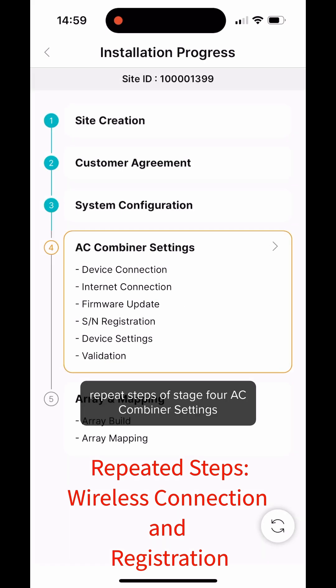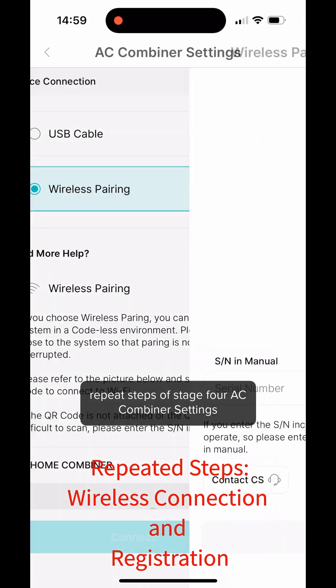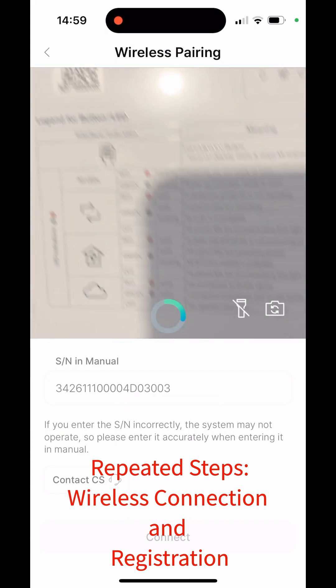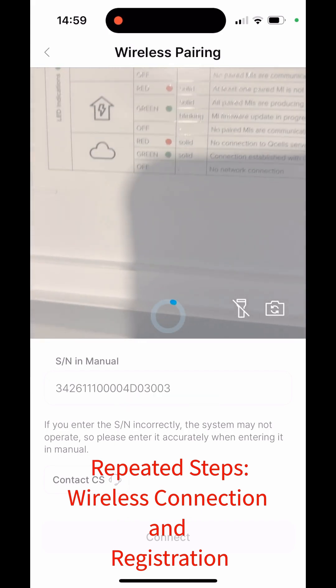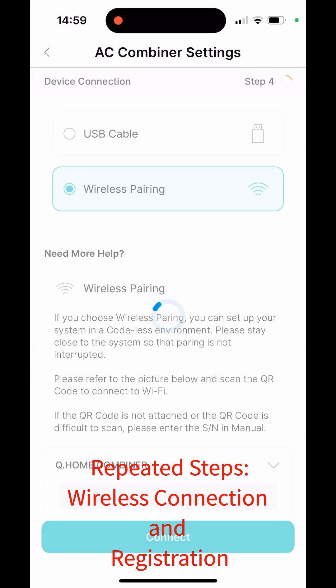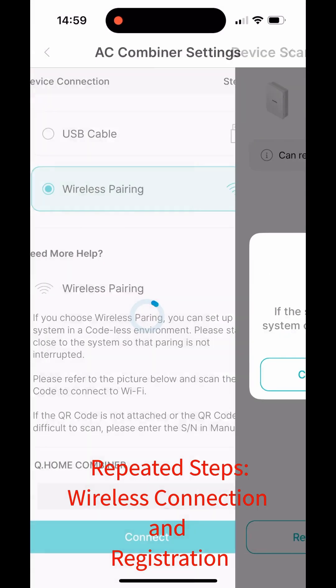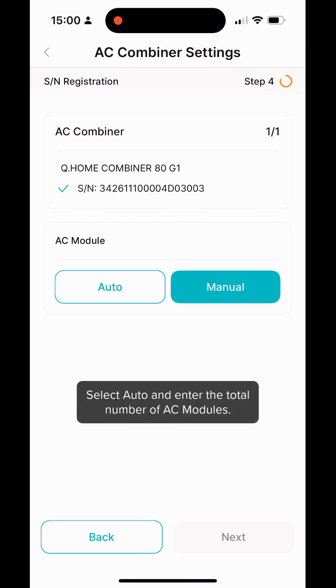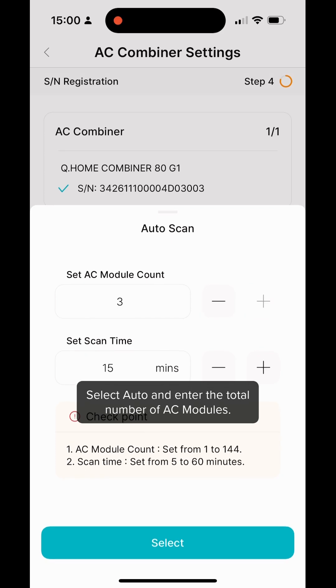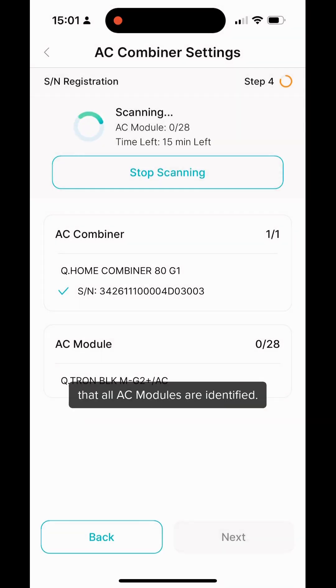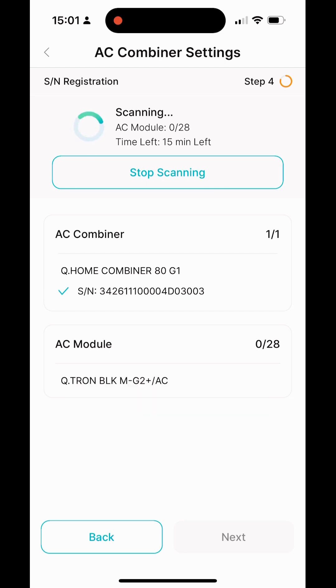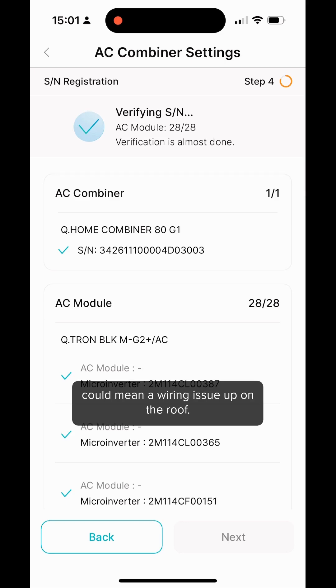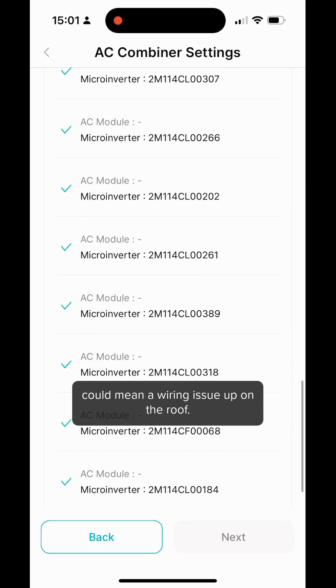After the update, repeat steps of stage 4 AC Combiner settings up to this point. Select Auto and enter the total number of AC Modules. The AC Combiner will scan to confirm that all AC Modules are identified. A failure to scan an AC Module could mean a wiring issue up on the roof.